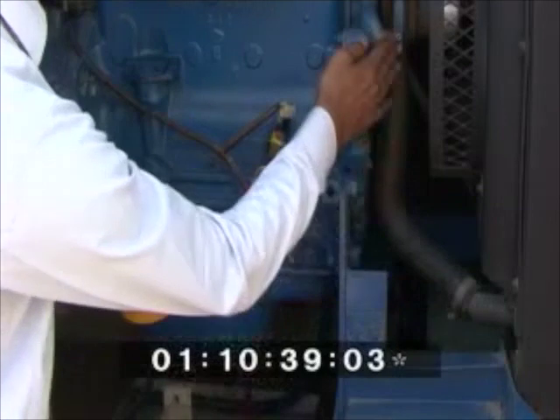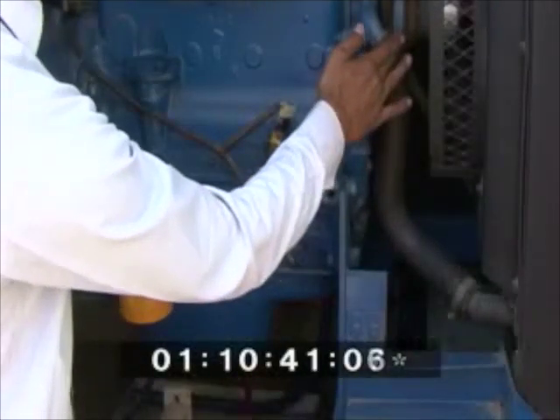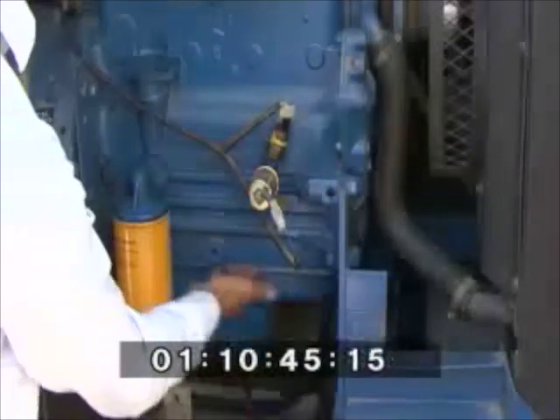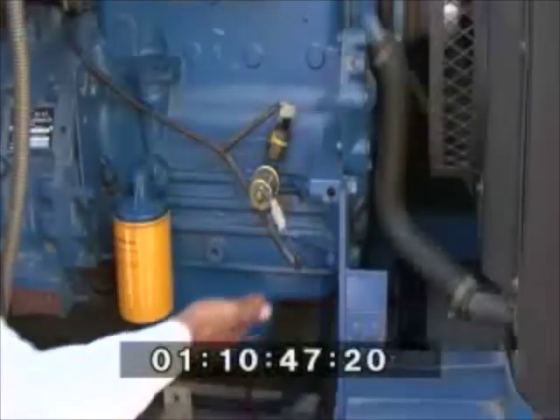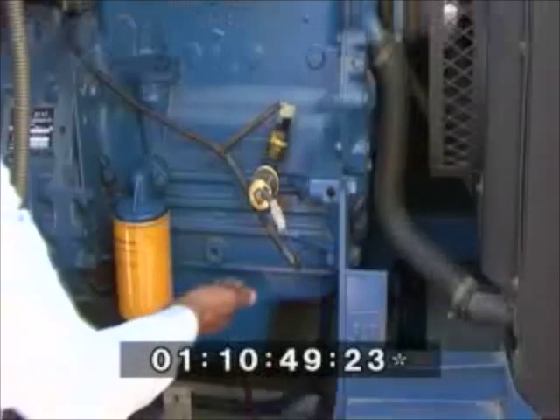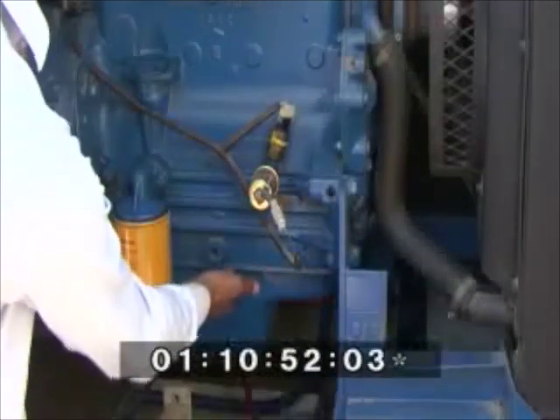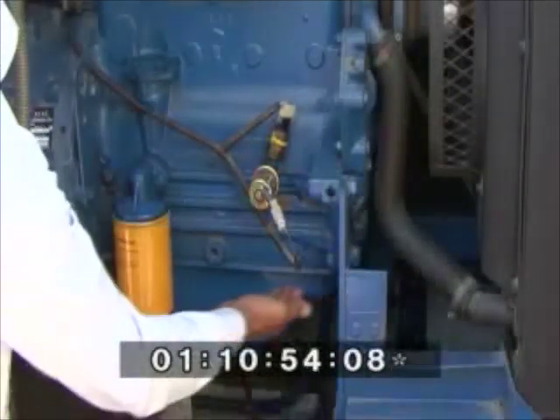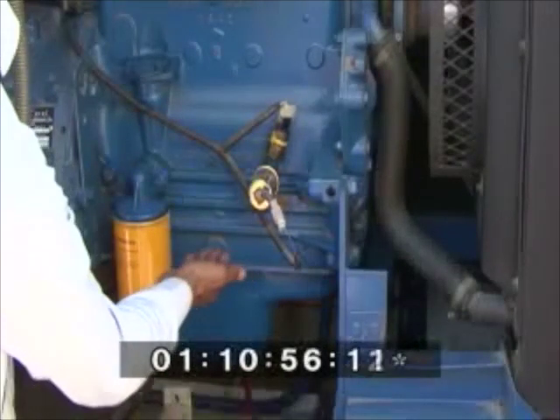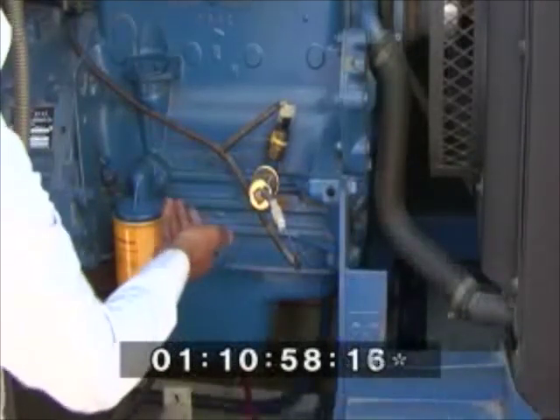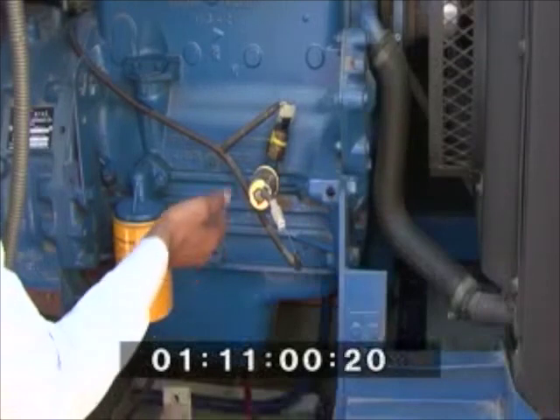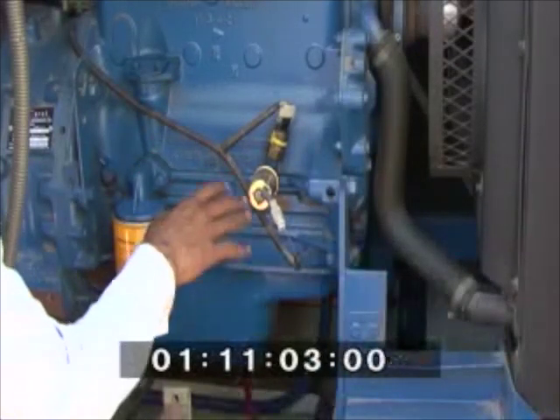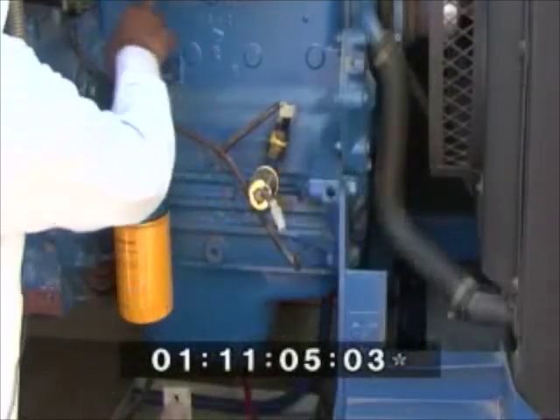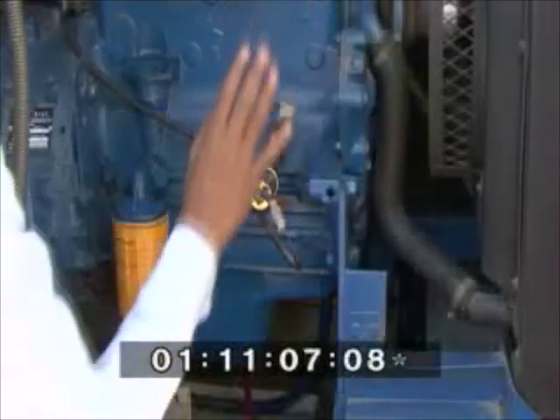In case the leakage is from the joints of the chamber, we will check the gaskets for any damage. In case the gasket is damaged, we will have to repair the same. So, we need to check all the joints on the chamber for oil leakage.